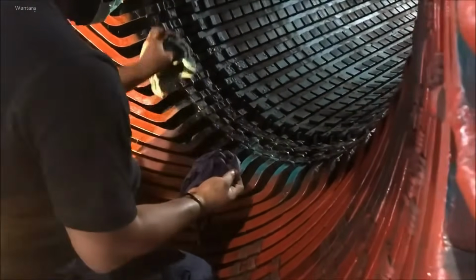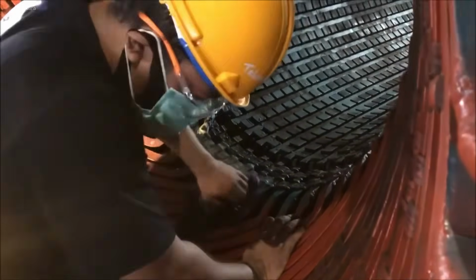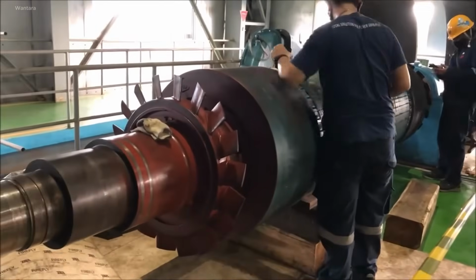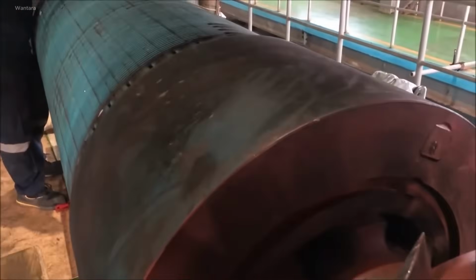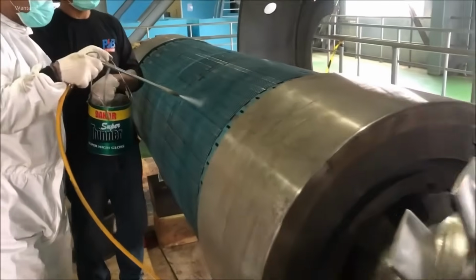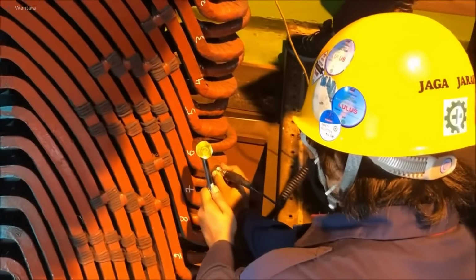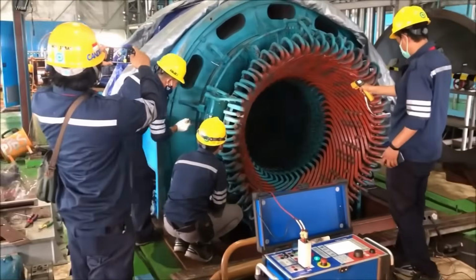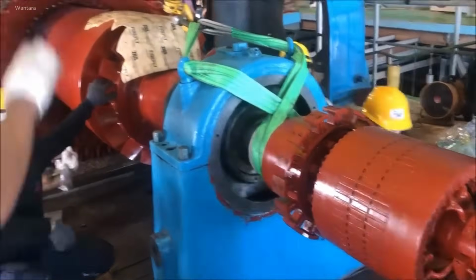Technicians check the wedges for tightness and integrity. A bump test is conducted on the stator end windings to detect any looseness or vibration issues. Finally, the rotor and stator are revarnished to restore insulation and protect against future degradation.